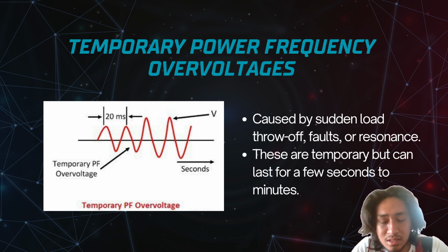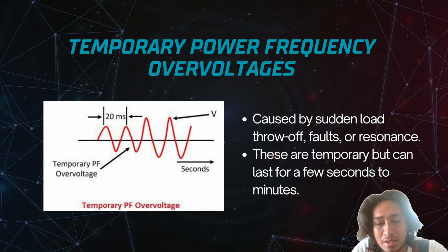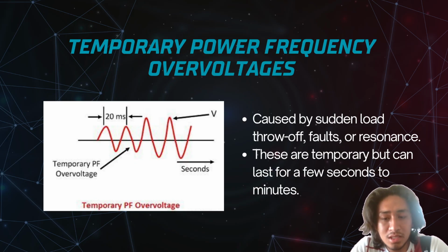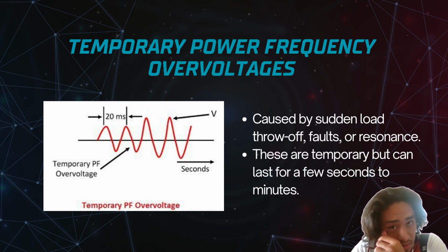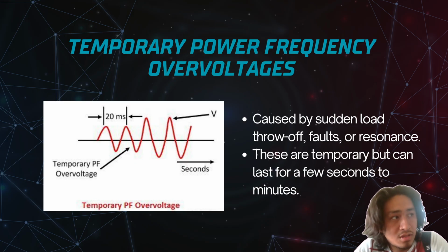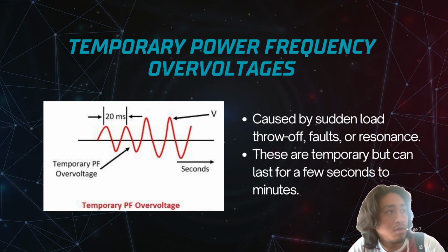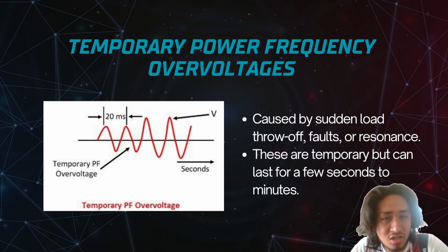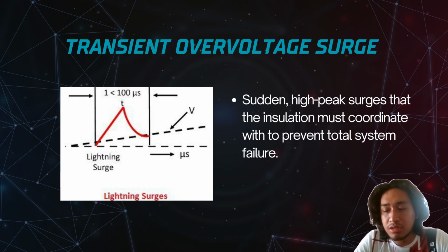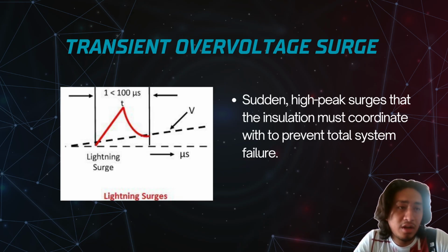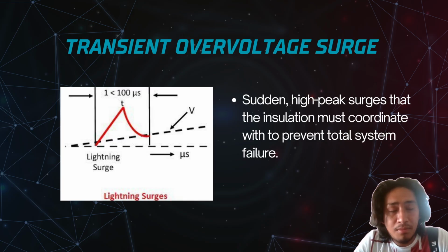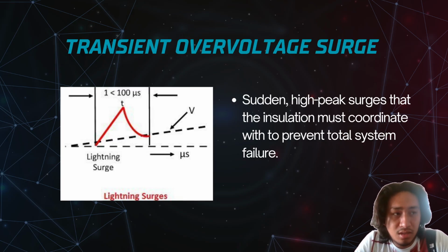Then compared to lightning, as I mentioned earlier, this lasts a long time, allowing it to cause significant damage to electrical infrastructure, since our electrical infrastructure is exposed to this phenomenon for a longer time compared to a transient. In the next slide is what we call transient overvoltage surge. So you are familiar with what a transient is, right? A transient is like a transition before it reaches its steady state condition.